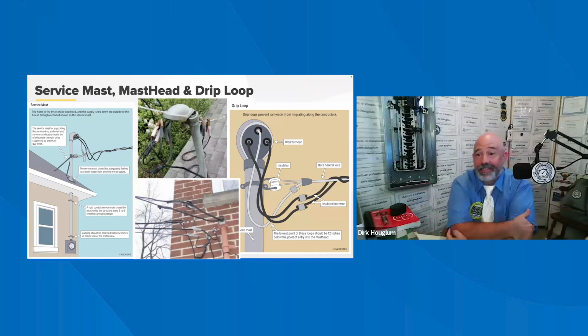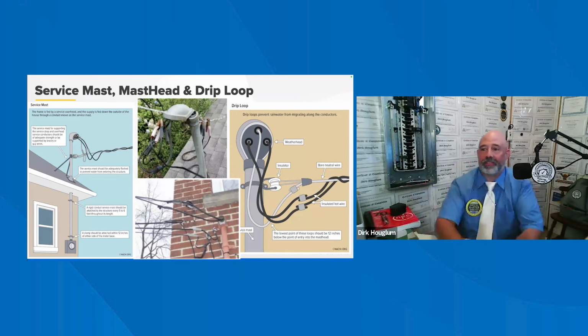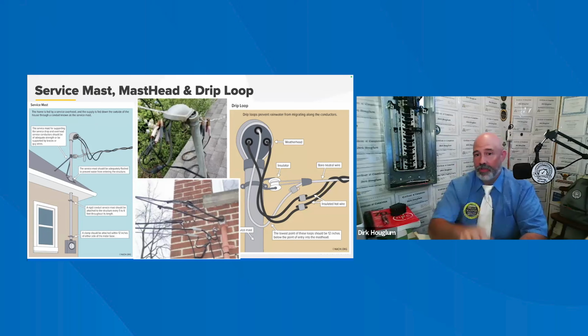In most cases, where the home is fed by a service overhead, the supply is fed down the outside of the house through the conduit known as the service mast. In some cases, the cable assembly is the type SE, which requires no conduit. The mast head, or gooseneck, as it's sometimes called, I like to call it a gooseneck, is at the top of the mast itself. Its purpose is twofold.